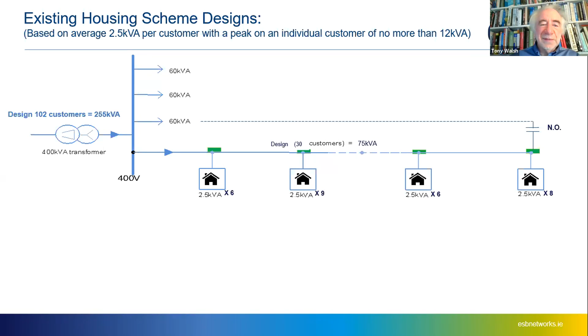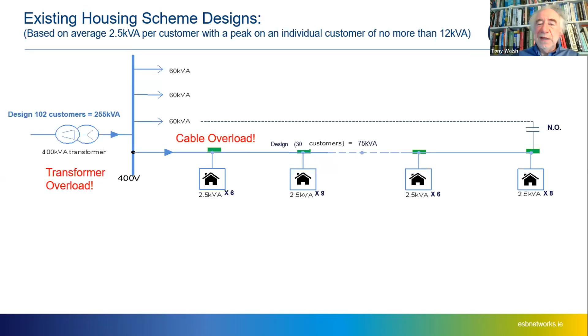However, that changes once you start putting in EVs and heat pumps, because the original design was based on the statistical summation of multiple small loads. Now you have large loads with long duration that don't sum in the same way. This means we could have a transformer overload or a cable overload, leading to limitations in these circuits. We could also have low voltage at the end of the network, due to voltage drop along the cables and across the transformers. So those are the impacts we have to deal with.